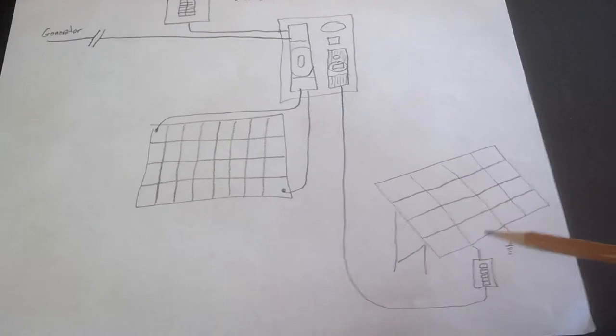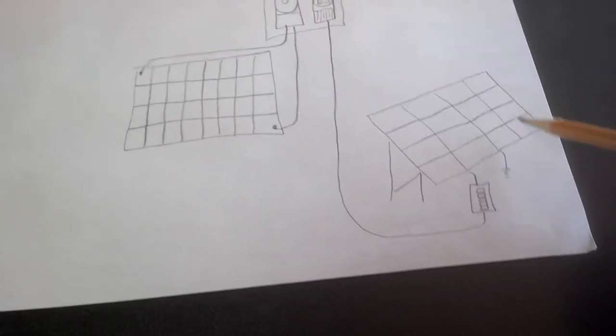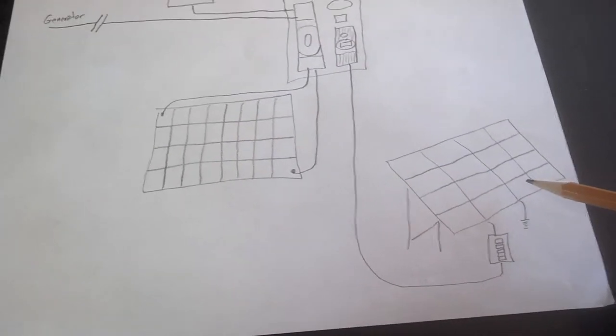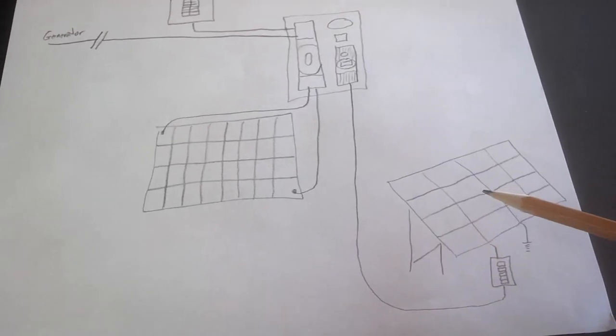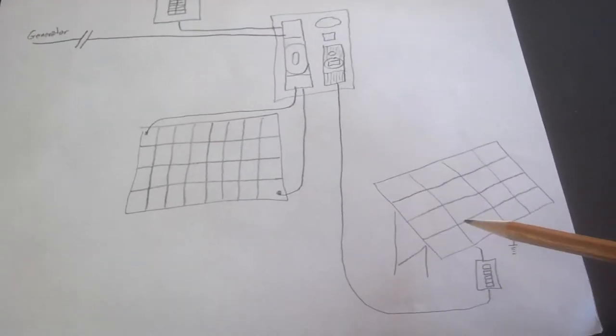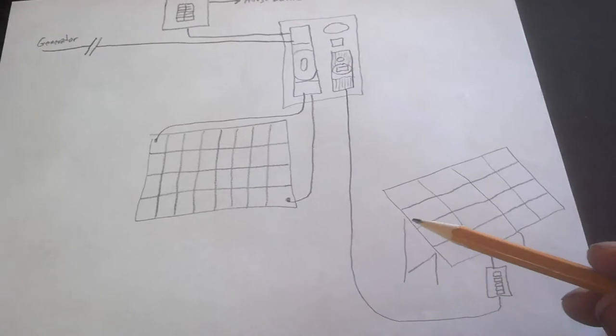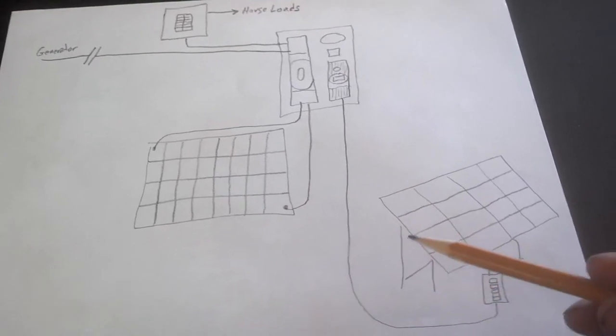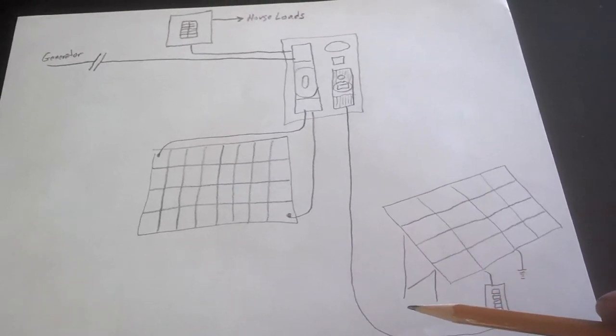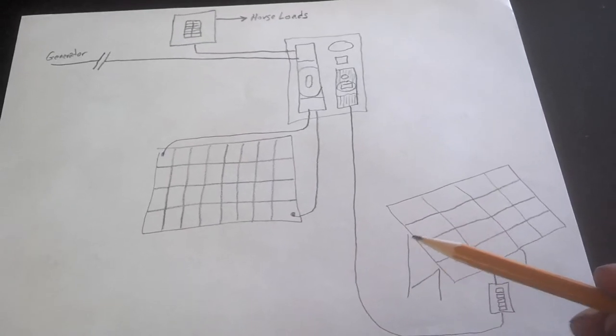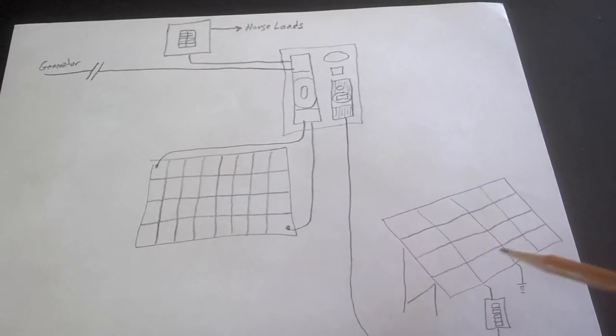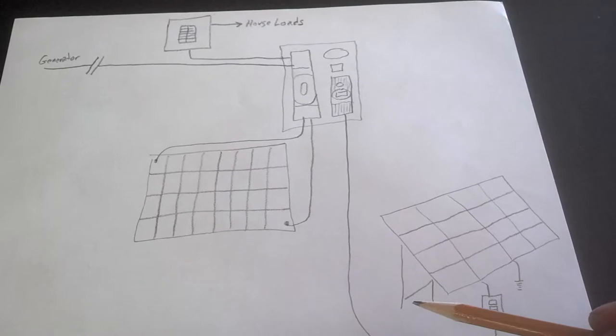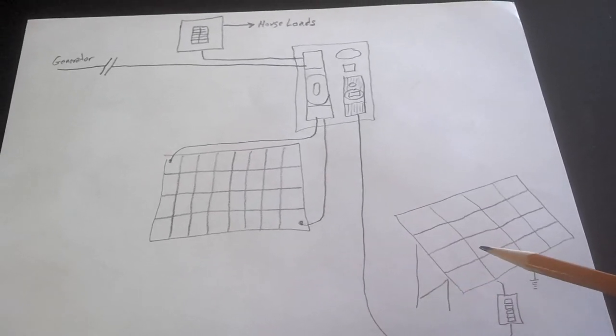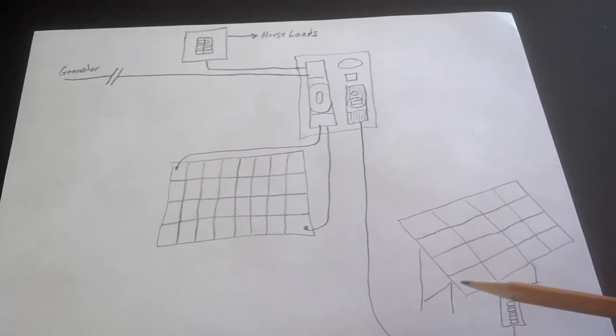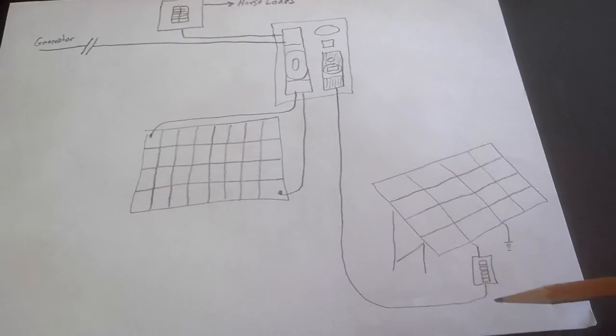This kind of shows 16 panels. We'll actually have 15, and that's due to the limitations of the charge controller. Get into that a little later. But anyway, ground mount, 2-inch schedule 40 galvanized pipe set into the ground, cemented in. Racks going across and braced back that way as well. We'll be using a product called Key Clamp to do that because we don't have a welder on site.